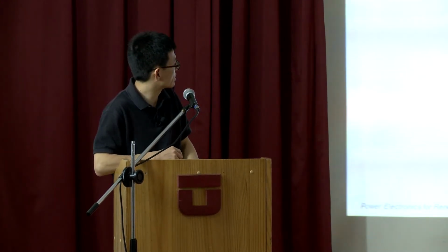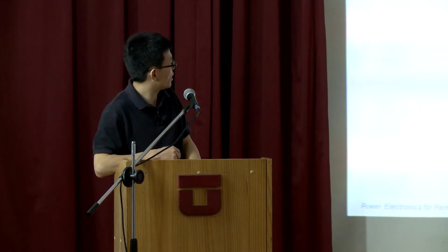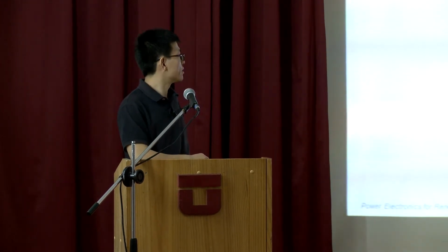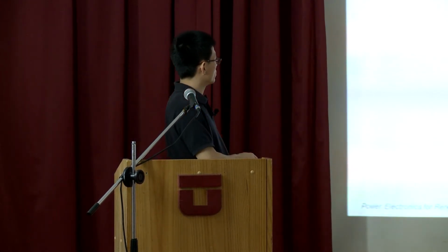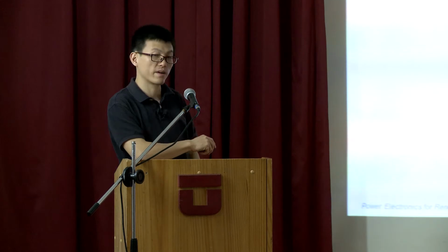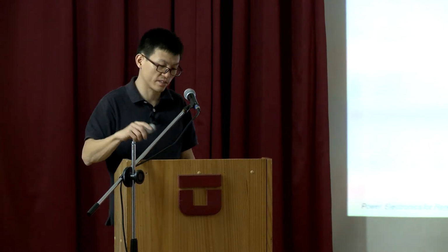The challenge is that this side is 270 volts and this is only 28 volts. So at the device level, going from 270 to 28 volts at 3 kilowatts means a current of about 100 amps, and reducing the ripple on this side is quite challenging. Also, paralleling GaN devices is very critical, because GaN devices on the market only come with low power ratings, so connecting them in parallel is very challenging.